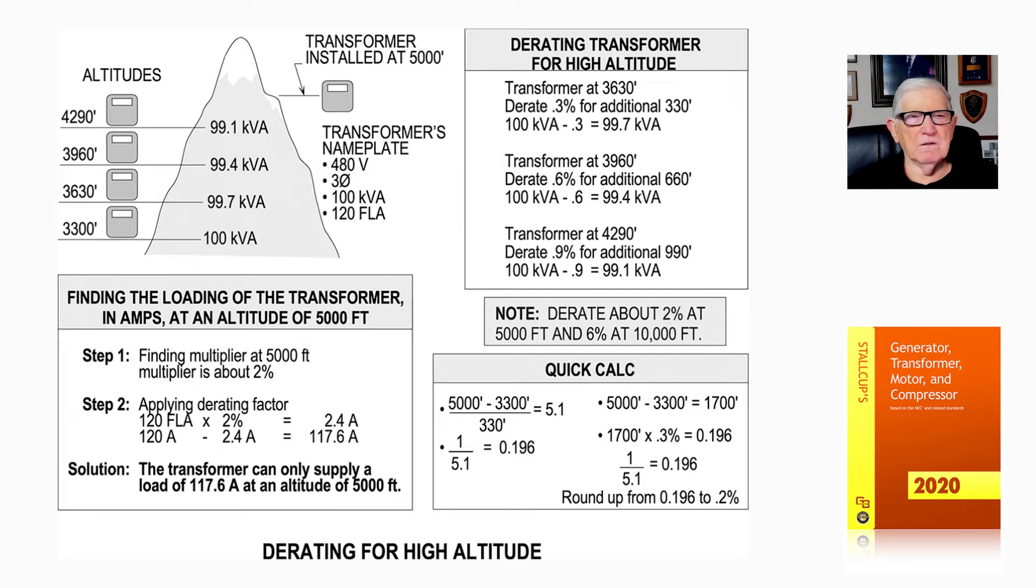At 4,290 feet it would be approximately 99.1 kVA. At 3,960 feet it would be approximately 99.4 kVA. At 3,300 feet it would be approximately 100 kVA. You're going to get the max amount at 3,300 feet and below.